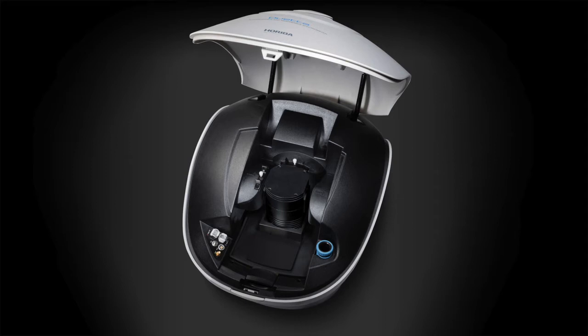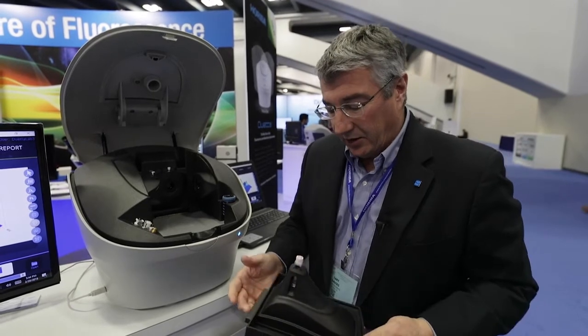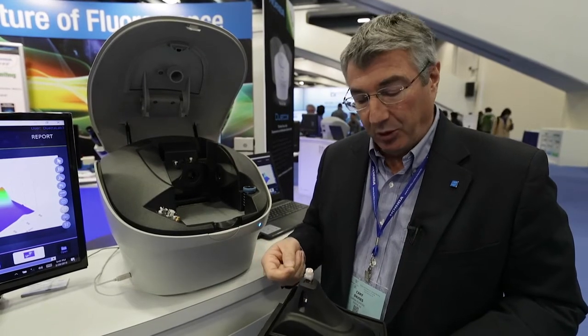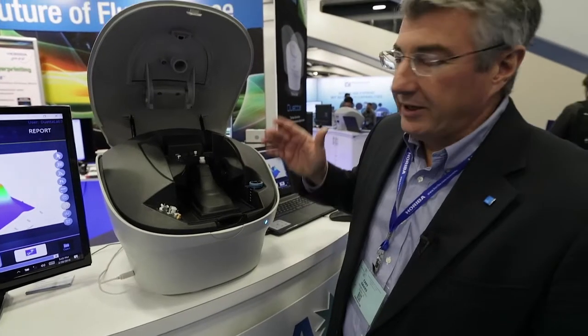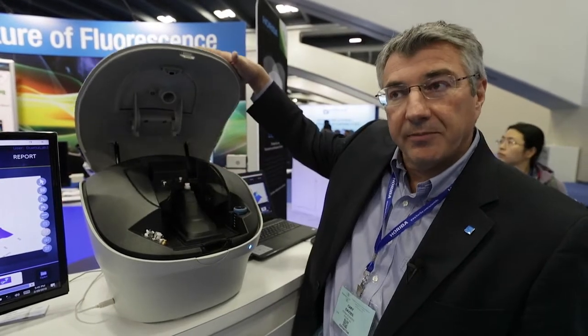What's unique about these trays is they have an electrical contact which is made when the tray slides into the instrument. This allows the software to recognize what type of sample holder is in place, and these contacts provide control and power — for a stepper motor if we have a four-position turret, for a stirrer in some sample holders, and any signal being measured like temperature can also be read when the tray is inserted. No tools are required — you simply slide it in, and EasySpec recognizes the instrument configuration and sample holder automatically.